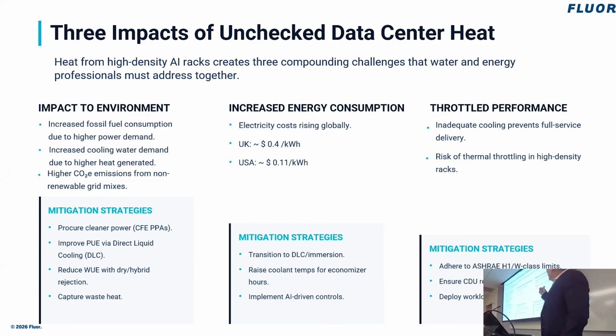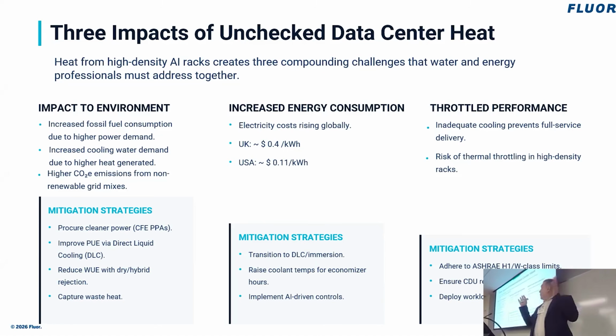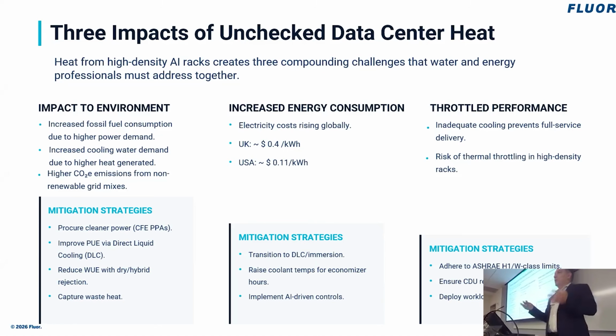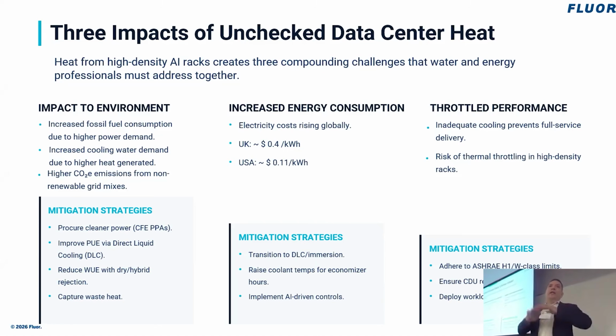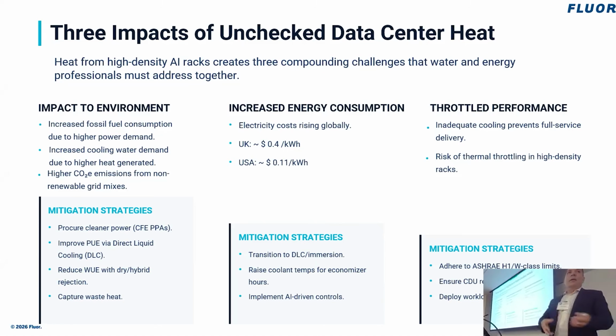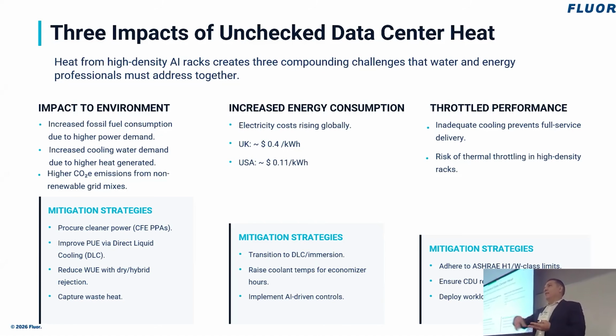To optimize heat recovery, one strategy is transitioning from direct liquid to chip using water, to an immersion system using what some of you may have heard of as a dielectric fluid. When this fluid is in contact with heat, it just evaporates, so we have a change of phase, and the gas is recovered and passed through a condenser to become liquid again.